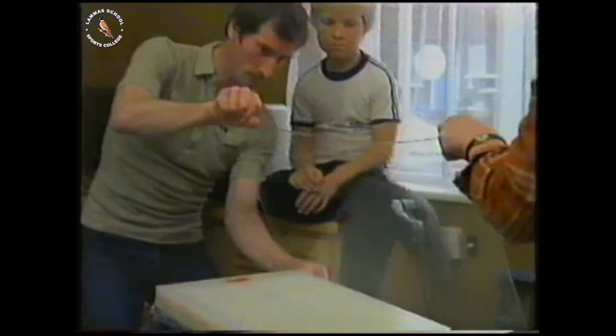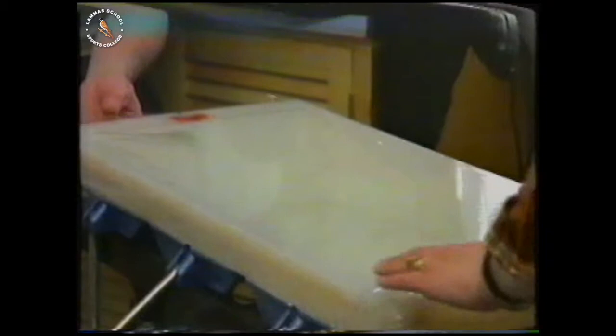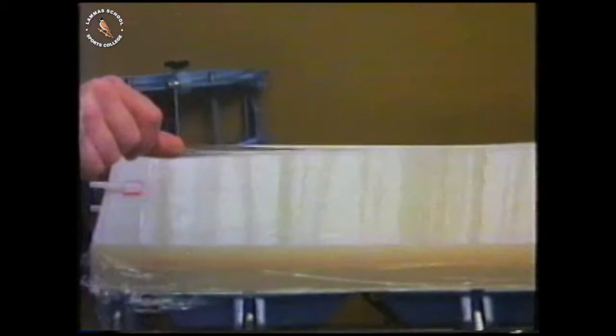This is another kind of artificial kidney — a larger version of the one in the hospital. It's put together by sandwiching sheets of cuprophane between thick plastic slabs. Blood will come in through one tube and leave through another. A second sheet of cuprophane is put over the first, making a sandwich through which the blood will flow. It has to be carefully stretched over to avoid trapping any air.